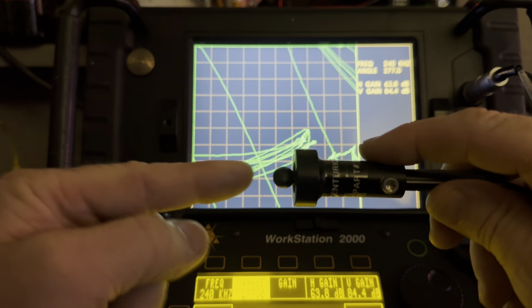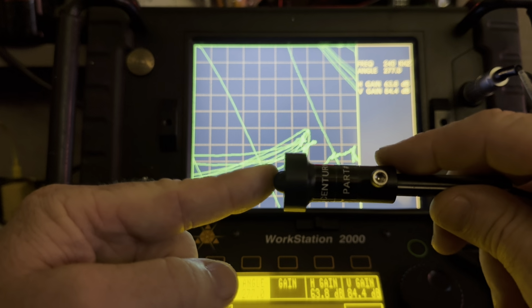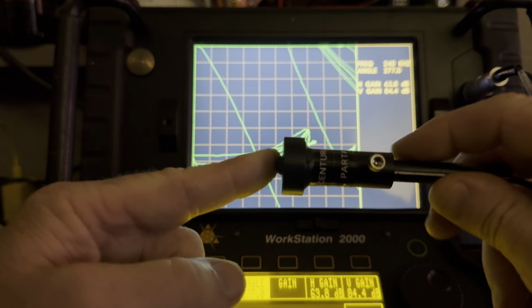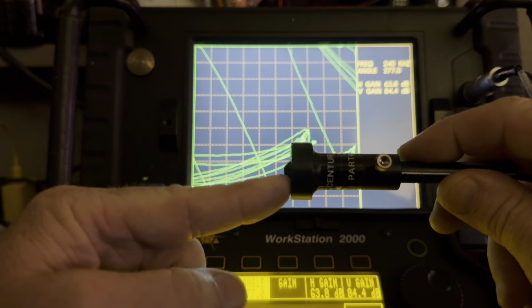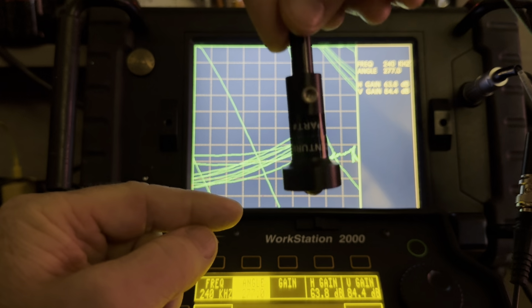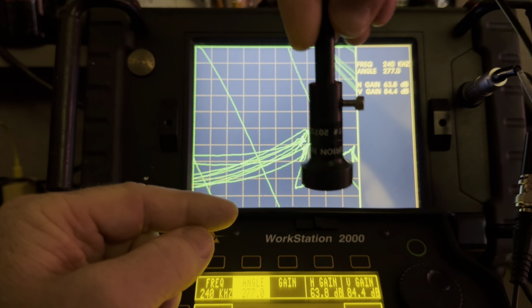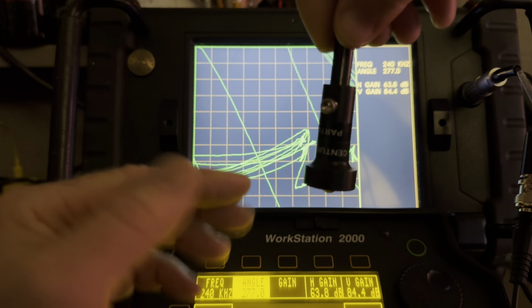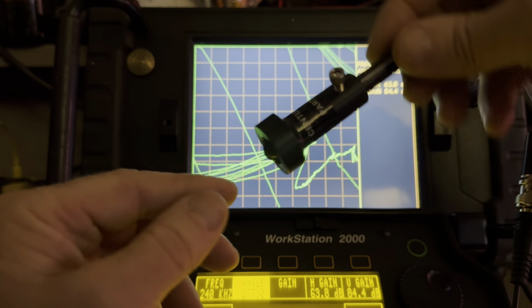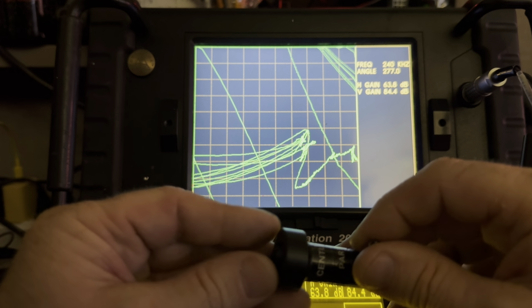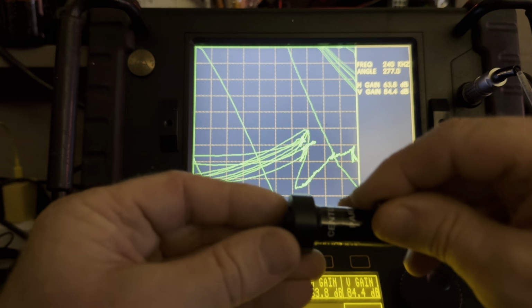So it might say, first, set it a quarter of the depth of the probe, and then tighten your set screw. And then what you'll do is you'll insert the probe, and then you'll scan 360 back and forth. And that'll be like your first layer of the hole. And I've got to keep in mind this pancake coil has a little bit of look ahead and look behind. So that may help out with the overlap a little bit.